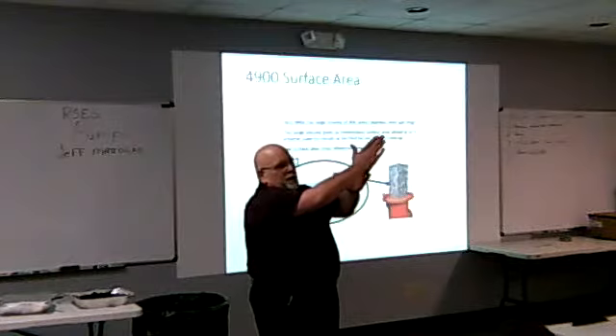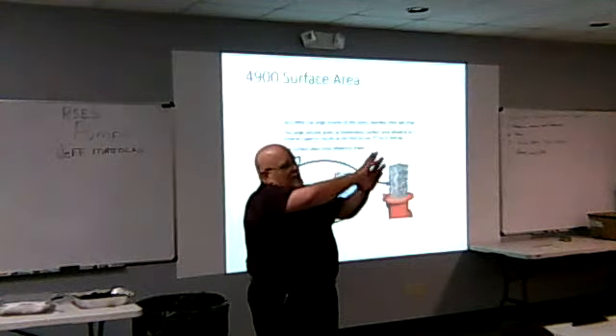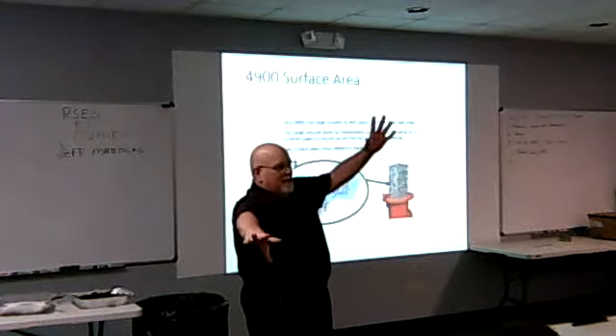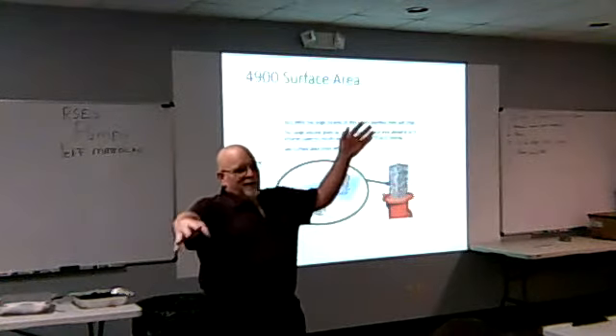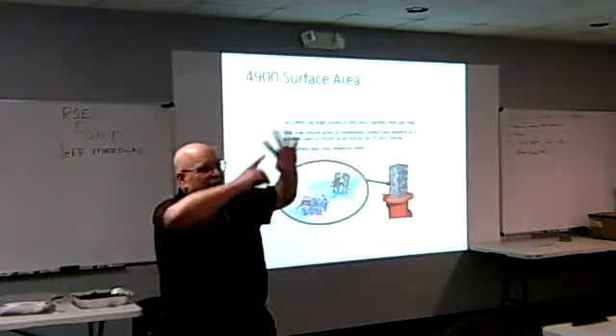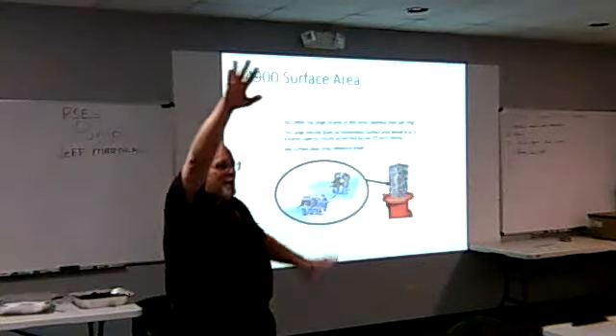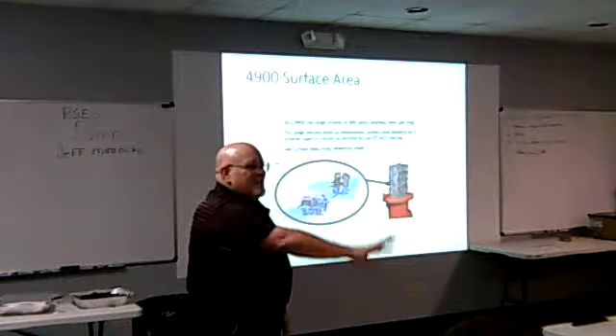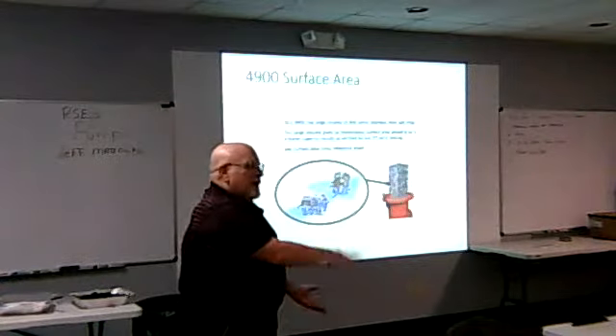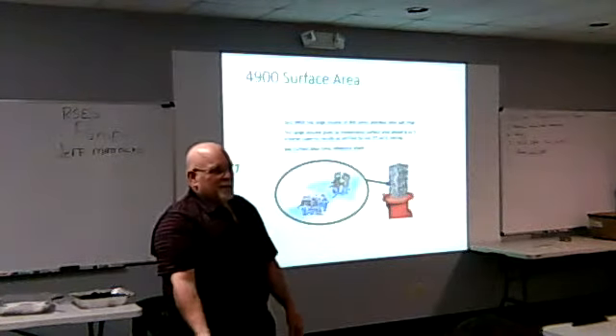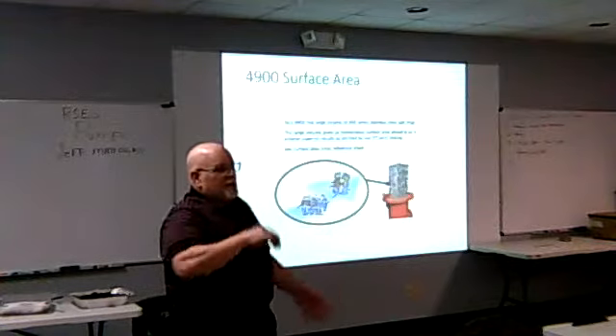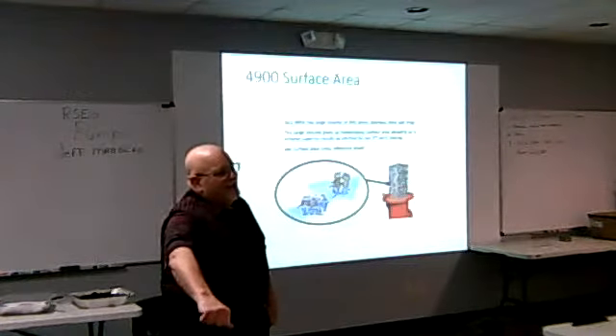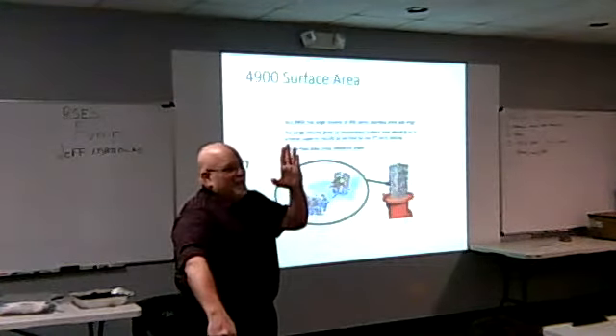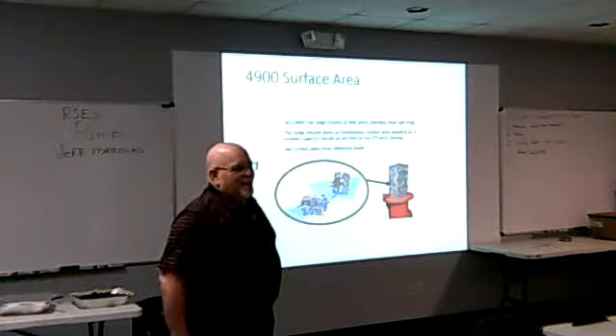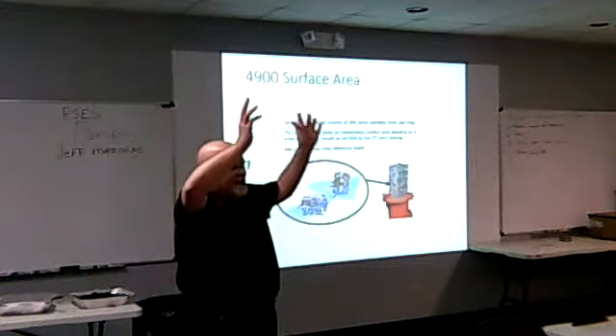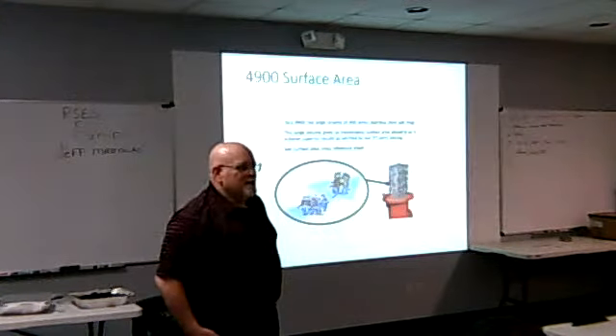The problem is, that's the design. Here on the curve, I only have 2 foot of NPSH. But that thing is trying to push against 10 pounds of head. I run way out here on the curve, then NPSH goes through the roof. My pump efficiency does what? Falls off. Now I'm at 20% pump inefficiency. I'm damaging the impellers and I'm not pumping. But if I had a ball valve there, guess what? I throttle back until that gauge goes to 50. Voila. Our pumping efficiency went to 100, just like our condenser used to do.